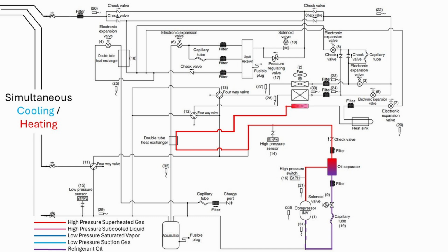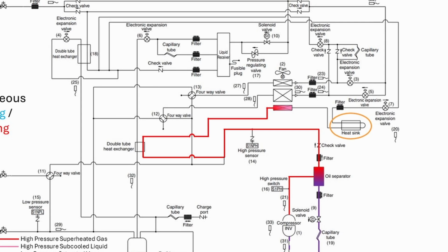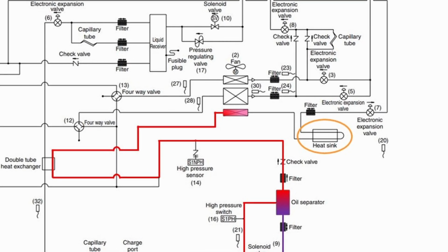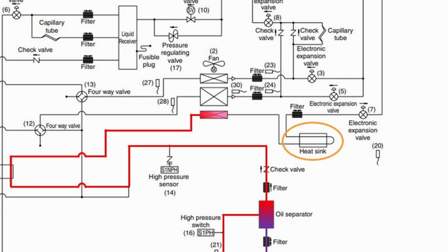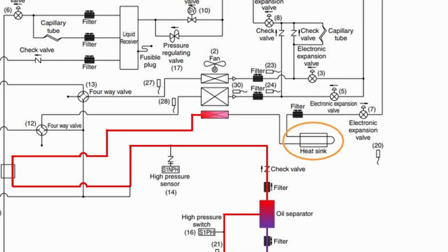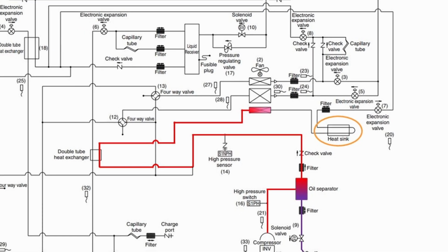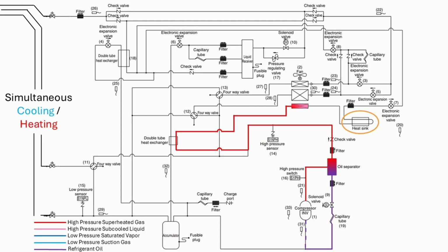As the outdoor unit runs, the inverter board will create heat in the section where the DC power is converted into a 3-phase AC to run the compressor. The outdoor unit refrigeration circuit directs subcooled liquid through a heat sink to cool that inverter board. Since the system currently is requiring more heating than cooling, this 4-way valve is directing refrigerant to the smaller of the 2 remaining sections of outdoor heat exchanger, reserving the larger section for the heating mode.